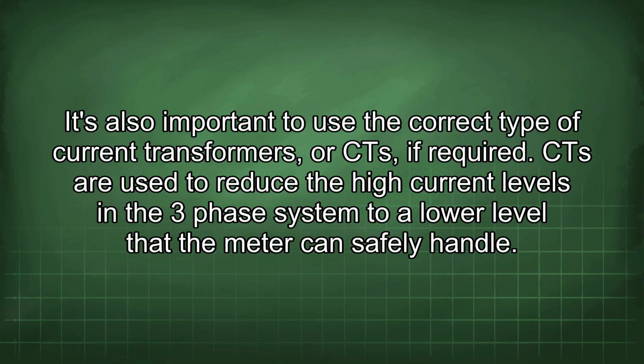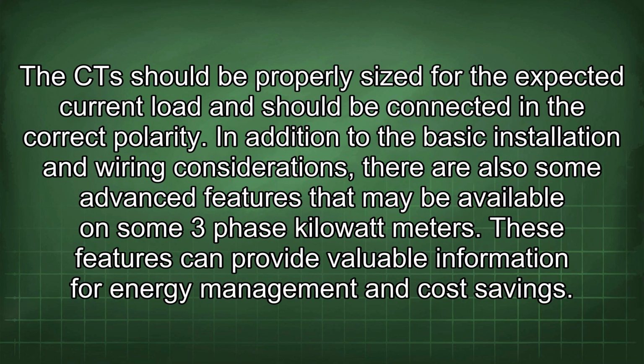CTs are used to reduce the high current levels in the three-phase system to a low level that the meter can safely handle. The CT should be properly sized for the expected current load and should be connected in the correct polarity. In addition to the basic installation and wiring considerations, there are also some advanced features that may be available on some three-phase kilowatt meters.